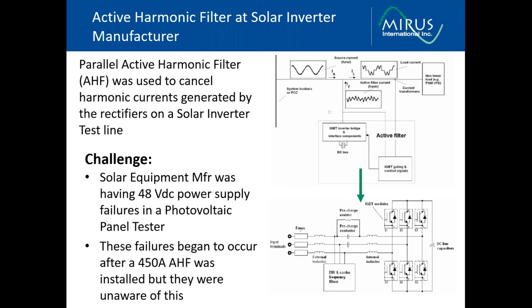These failures began to occur after a 450 amp active harmonic filter was installed on another area of the plant where they were trying to reduce the harmonics generated by the rectifiers they were using to produce DC to test inverters that they built, solar inverters.